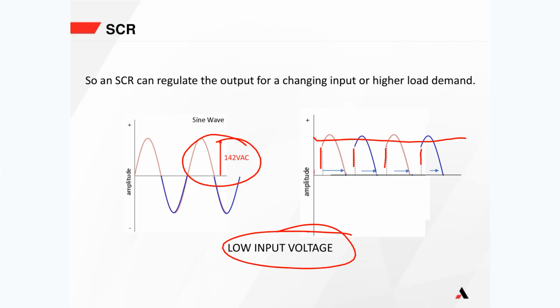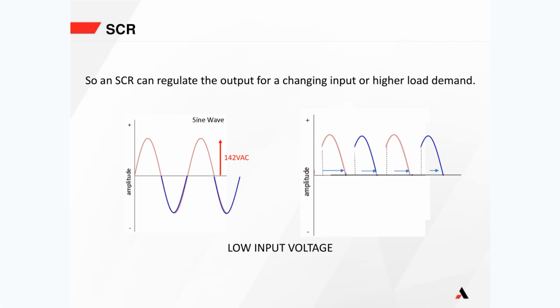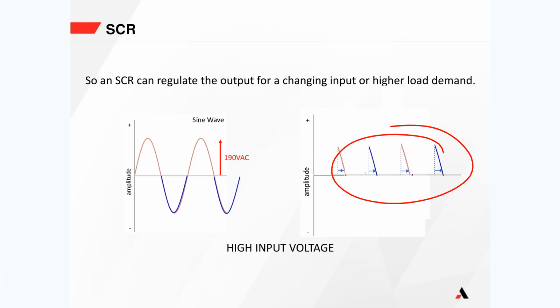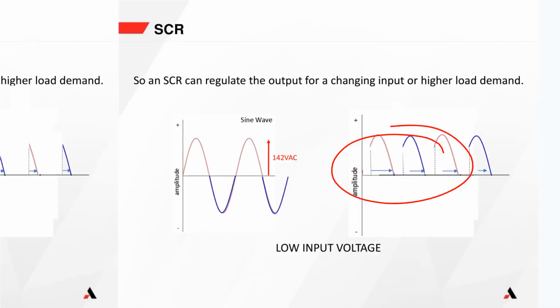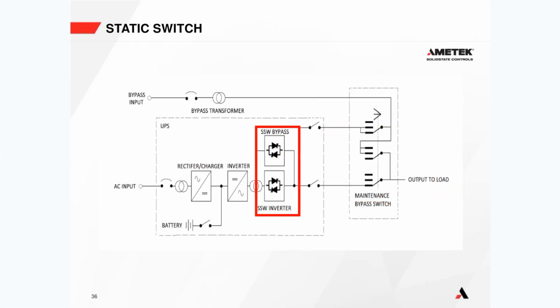And we are constantly doing this. That's what the feedback circuit I mentioned earlier does. It's always looking at the output voltage, after it goes through a capacitor and inductor to smooth it out. If that's 135 volts DC and we have a low input voltage, it will turn the SCRs on earlier in the sine wave. If we have a high voltage, it will turn them on much later in the cycle. That keeps the output constant at 135 volts DC.